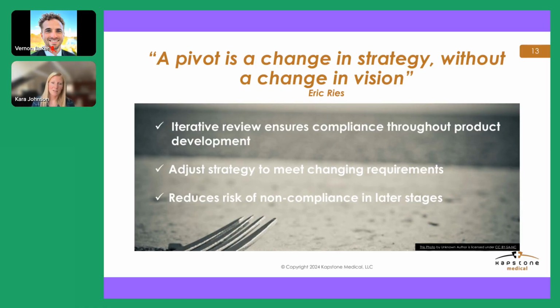As you get into prototype phase, a lot of this is sort of bridging the gap between concept into your development phase, which is usually phase 2, thereabouts. This phase reveals potential engineering and manufacturability challenges, which may impact the design, may in fact impact the actual functionality of the device, the user needs, definitely can impact your potential hazards associated with the use of the device, and it may even possibly impact your indications or intended use. You may have designed a really amazing product that doesn't do what you wanted it to do, but maybe it can still do something else. So not all is lost if you discover you're at this point and it didn't go quite as planned. Reassessment of the applicable standards, such as biocompatibility, electrical safety, software validation at this point in time, right in the prototype phase, is strongly recommended.